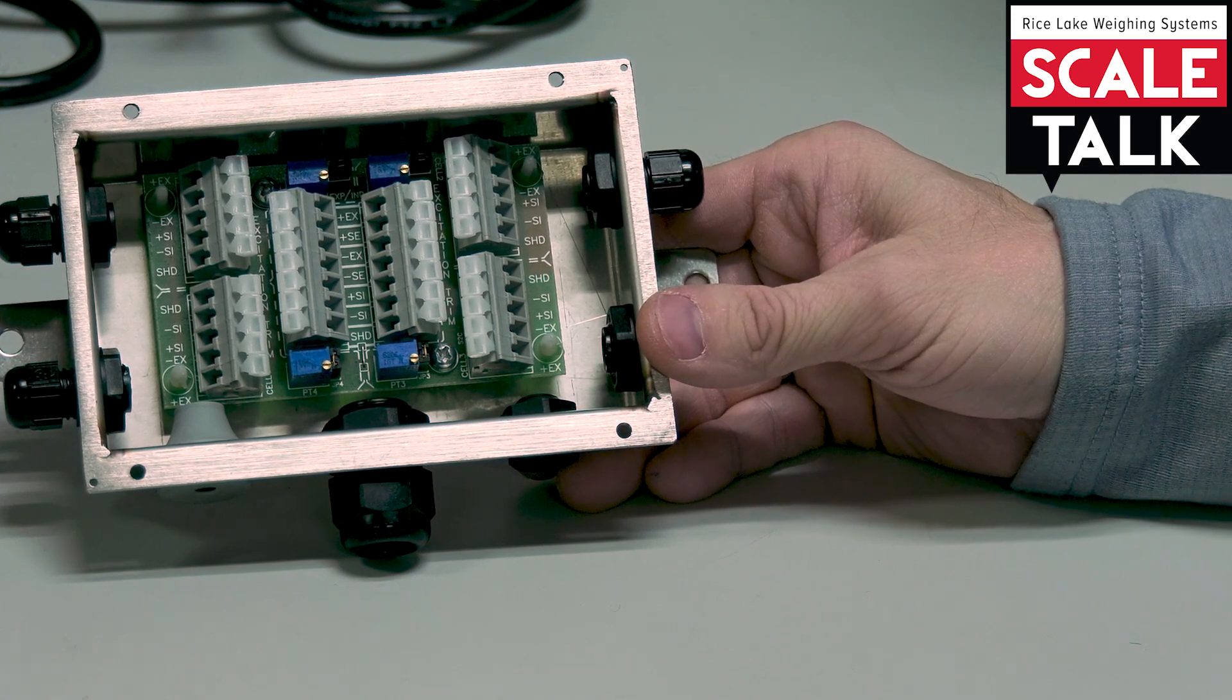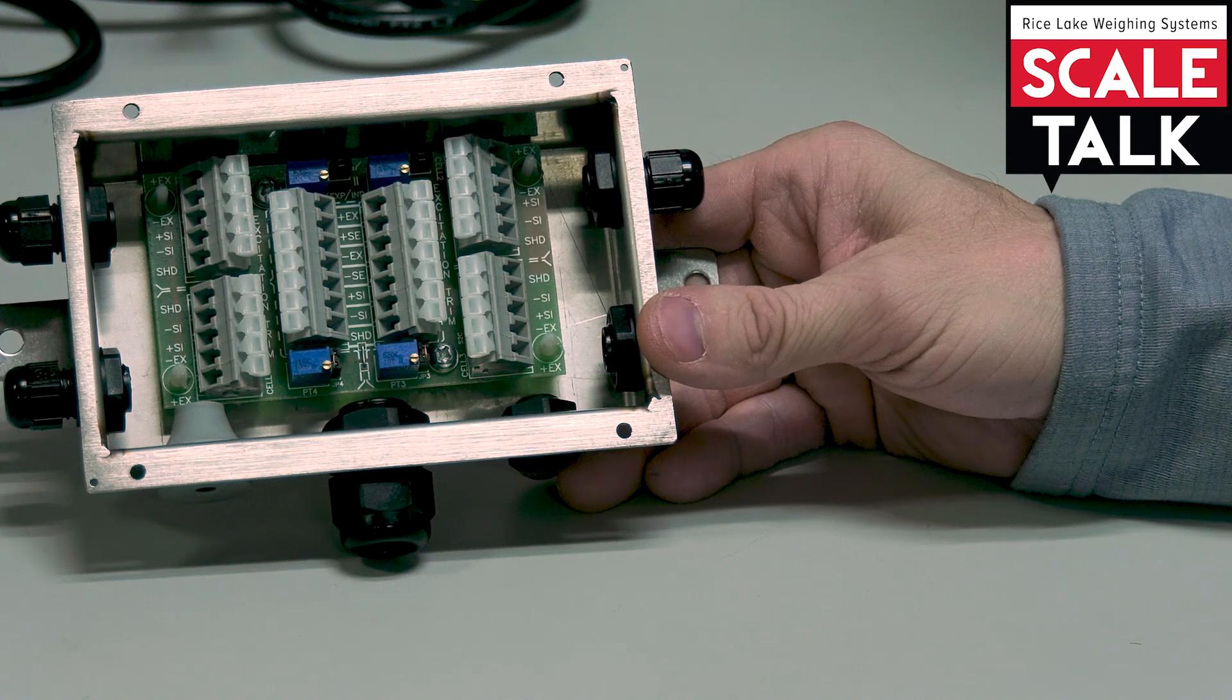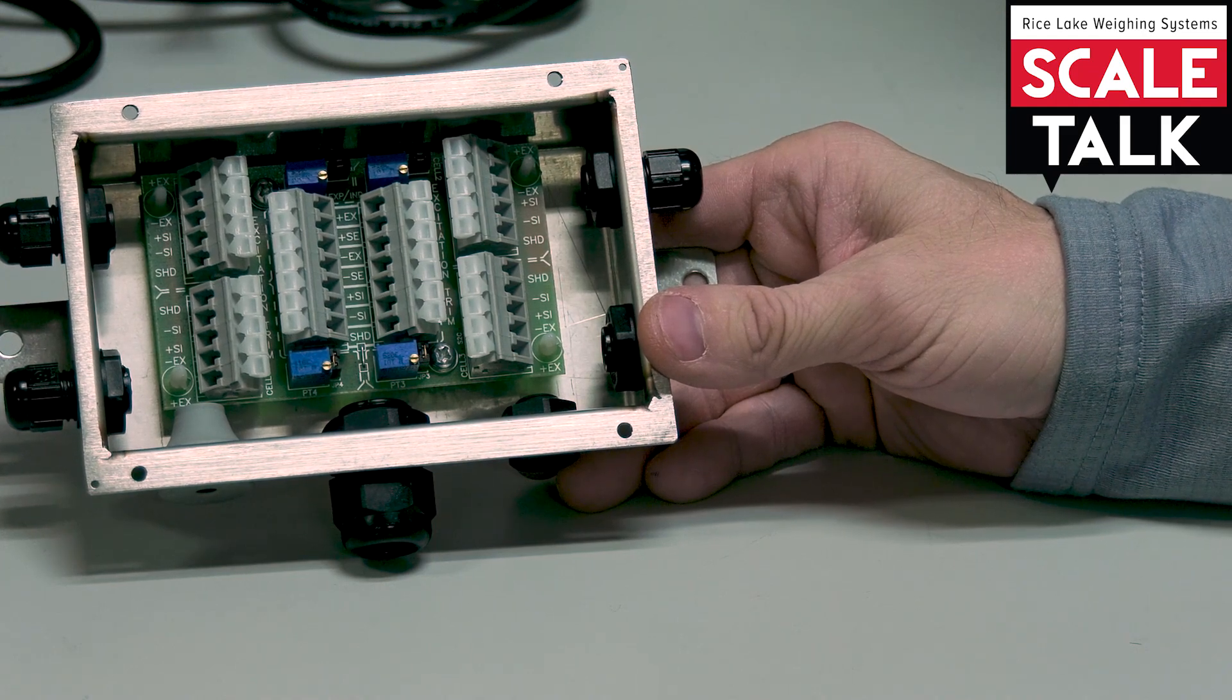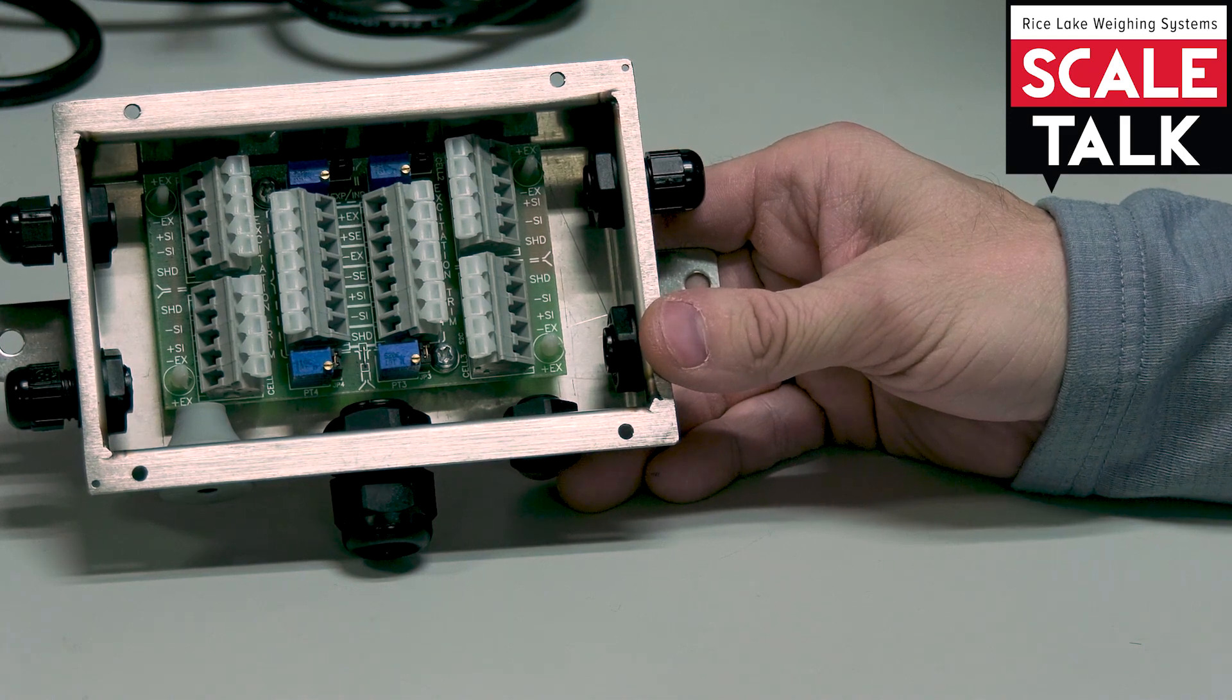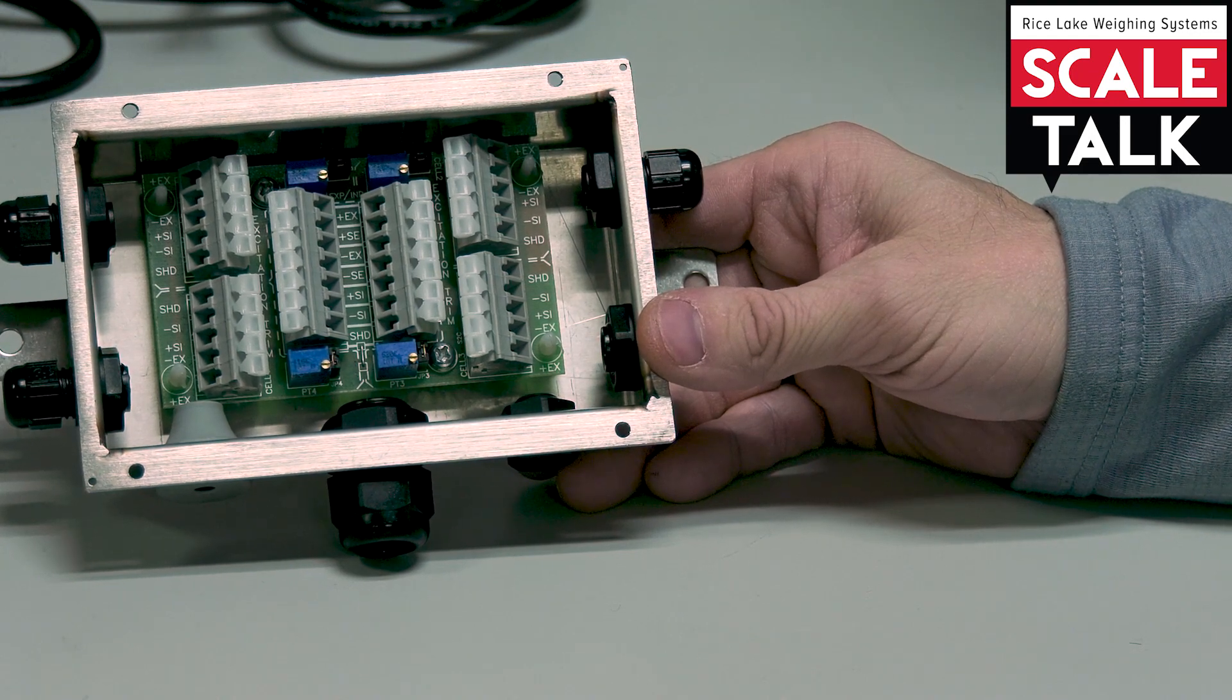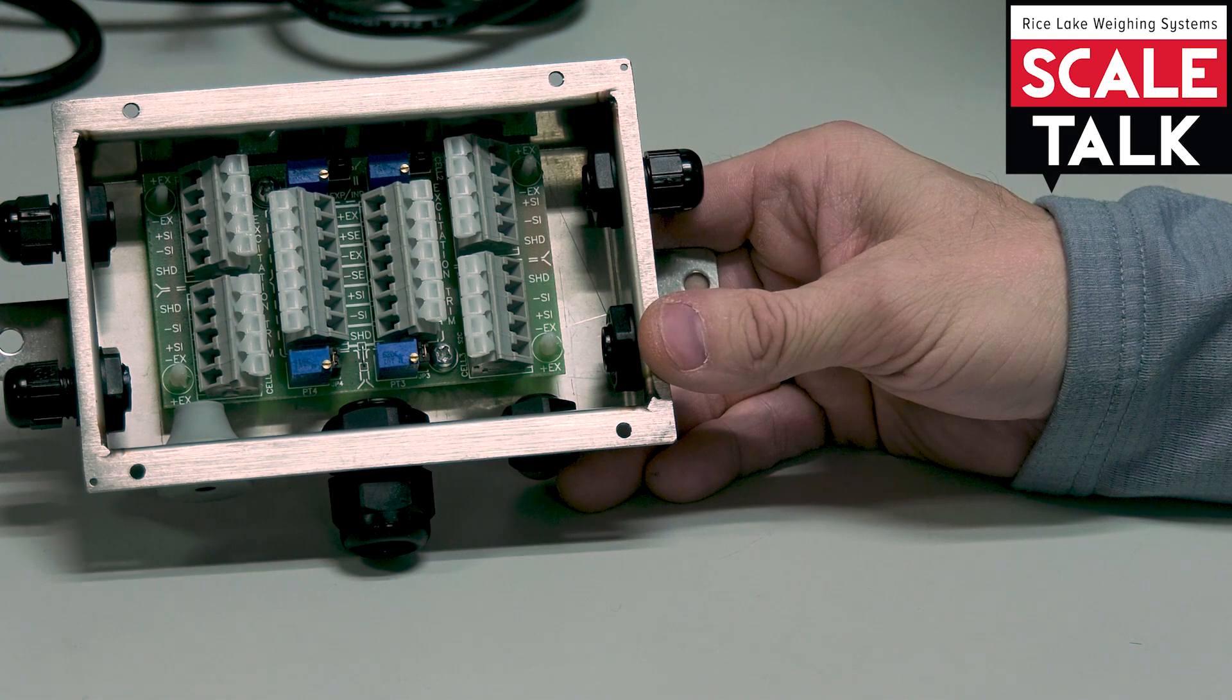Secondly, it allows us the ability to trim. Trimming is the act of creating the same signal-to-weight ratio between all of the load cells. Now you might look up in a catalog and find that a load cell has a 3 millivolt per volt value in terms of its rated output, but not every single load cell that you purchase is going to be exactly 3.0.